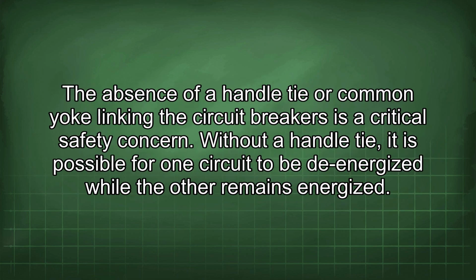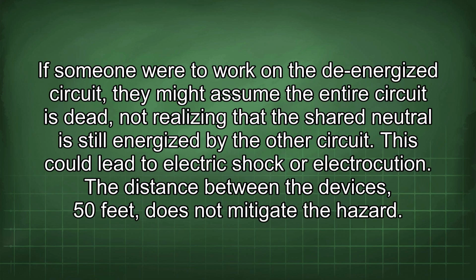The absence of a handle tie or common yoke linking the circuit breakers is a critical safety concern. Without a handle tie, it is possible for one circuit to be de-energized while the other remains energized. If someone were to work on the de-energized circuit, they might assume the entire circuit is dead, not realizing that the shared neutral is still energized by the other circuit. This could lead to electric shock or electrocution.